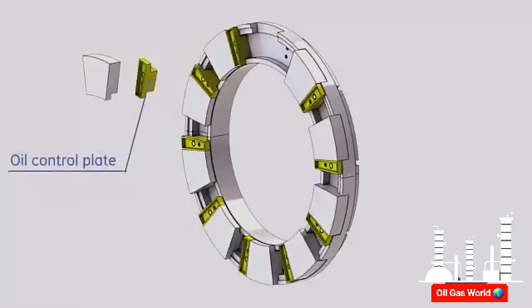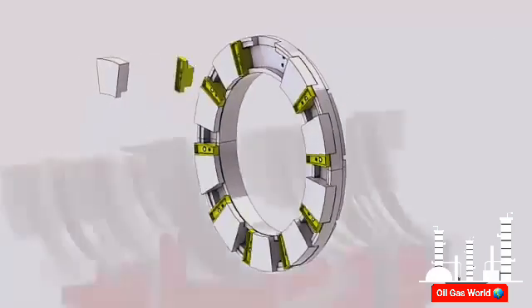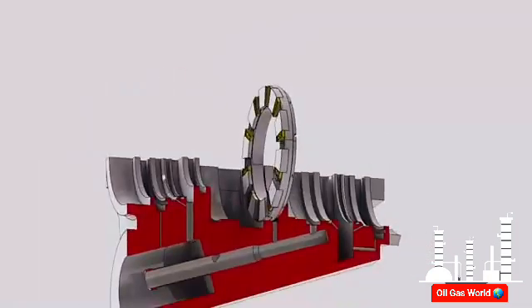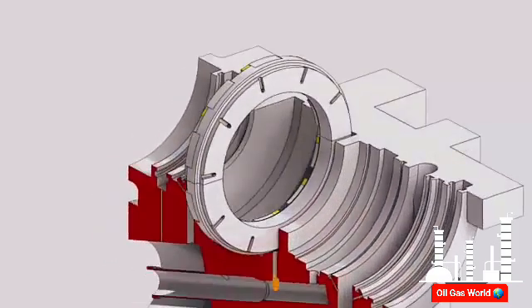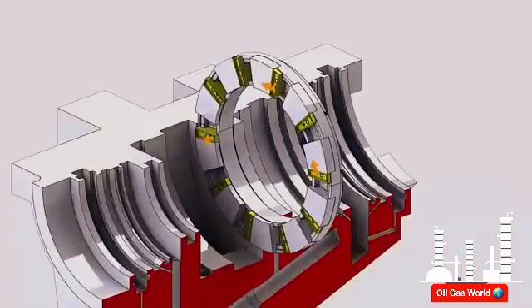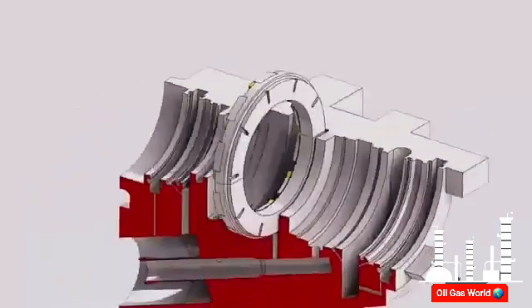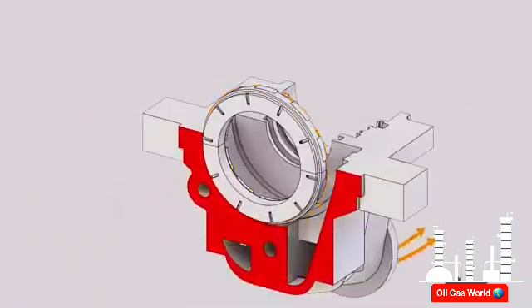Oil control plates are installed between pads. For lubrication, oil is supplied through the oil feed pipe to a port in the lower bearing housing, where the oil flows into annular space around the base ring. Then oil flows through holes on the back side of the base ring to the oil control plates, which introduce the oil directly to the bearing surface before each of the pads. Oil exits at the pad's periphery to the thrust bearing drain cavity to the lube oil drain piping.